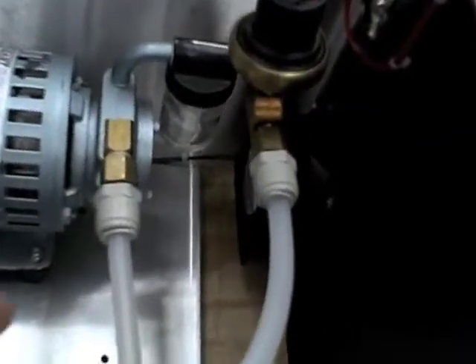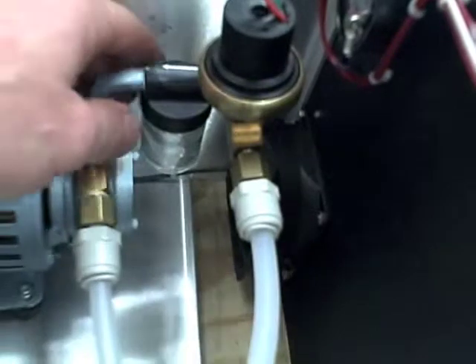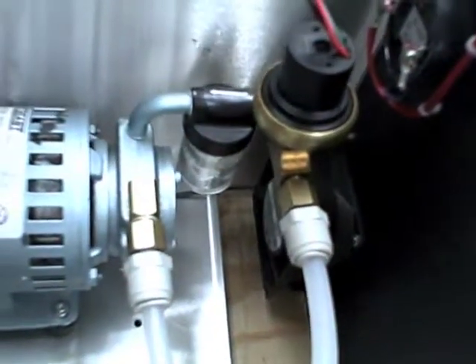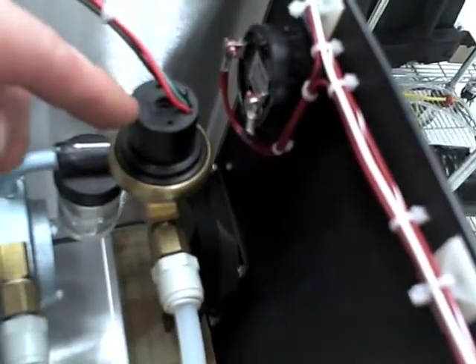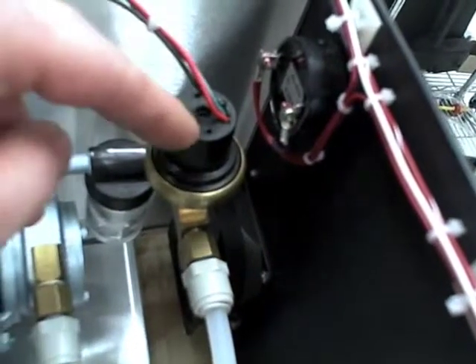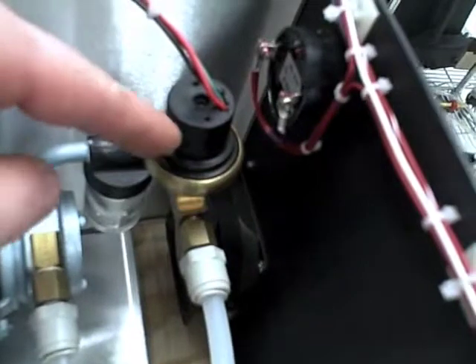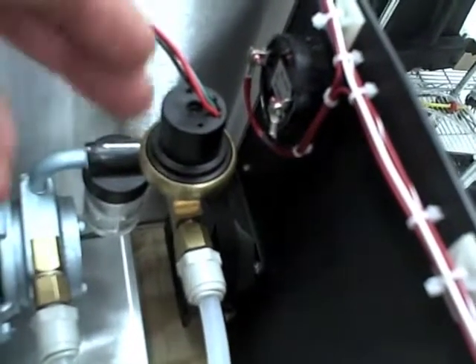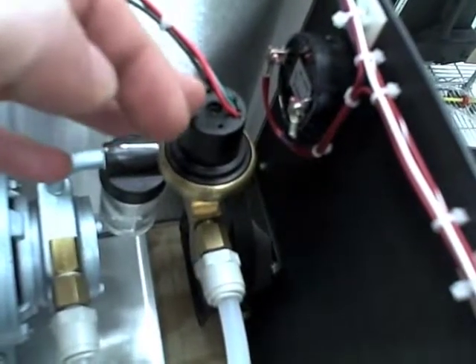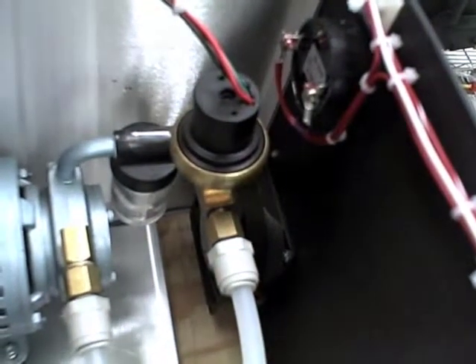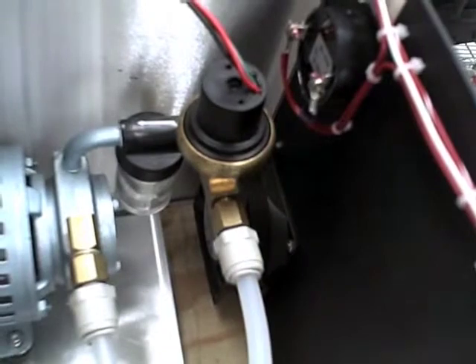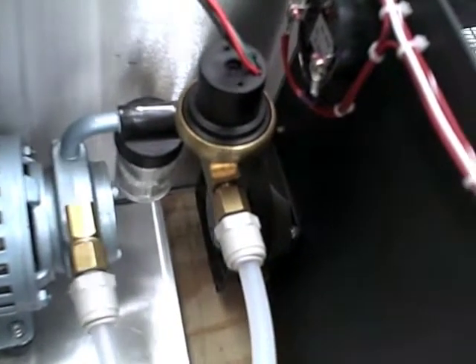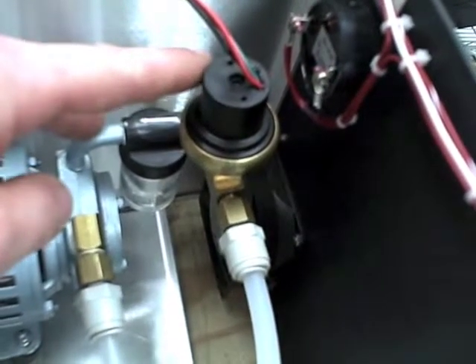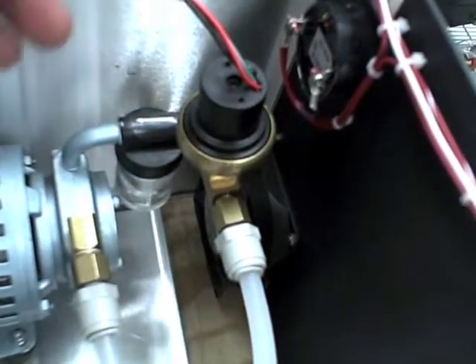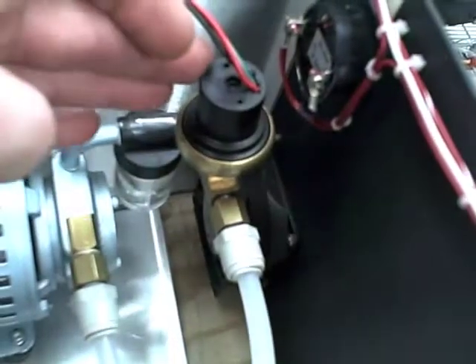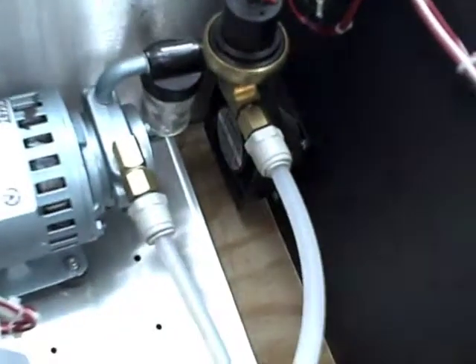On the front of the vacuum pump, you'll see a little glass canister, and the glass canister is just to collect any kind of debris that might get sucked in through the lines. And then the vacuum switch, and this also is another, it's going to be sensing the vacuum this time instead of the pressure like the other switch was. And if there is no vacuum pressure after the machine has been started, then this will signal to the PLC that there's no vacuum. There must be a problem somewhere. So let's shut the machine down to protect the operator from exploding glass, and that's the main reason for the fault conditions, just to protect the operator from exploding or imploding glass. So this is the vacuum switch, and that brings us around to the front of the machine again.